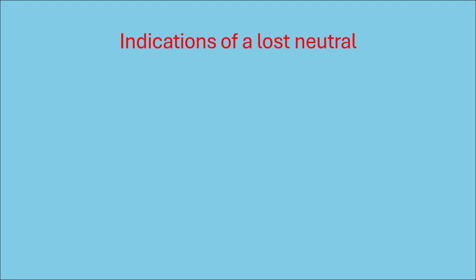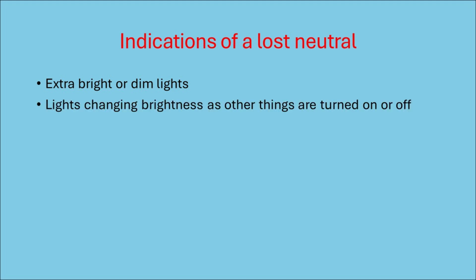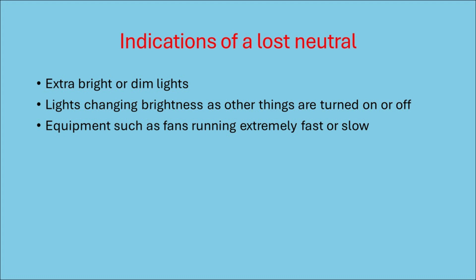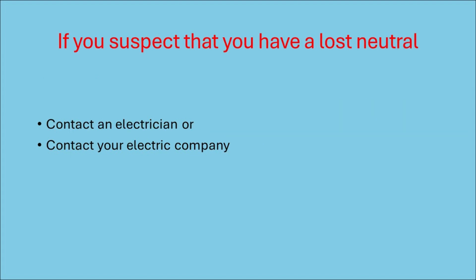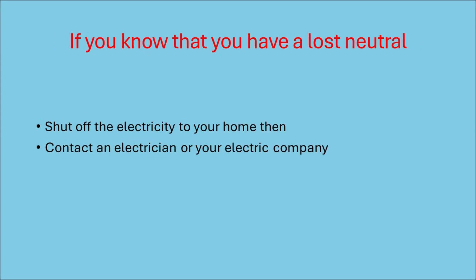So how do you know when you have a lost neutral? The main indication is lights burning dimmer or brighter than normal — lights that get dimmer or brighter as other equipment is turned on or off. If a fan or other piece of equipment seems to be running faster or more sluggishly than normal, you might have a lost neutral. If you suspect a lost neutral, you should immediately call an electrician or your electric company. If you feel quite confident that you've got a lost neutral, it's probably worth turning off the main breaker and killing the power to your house until someone gets out there to check it out.